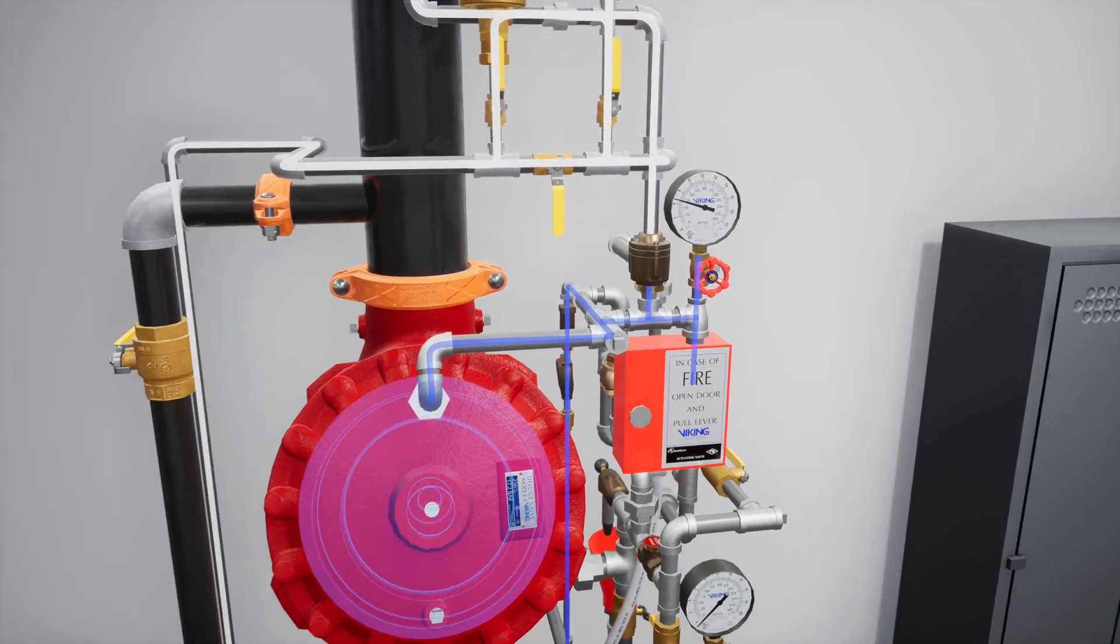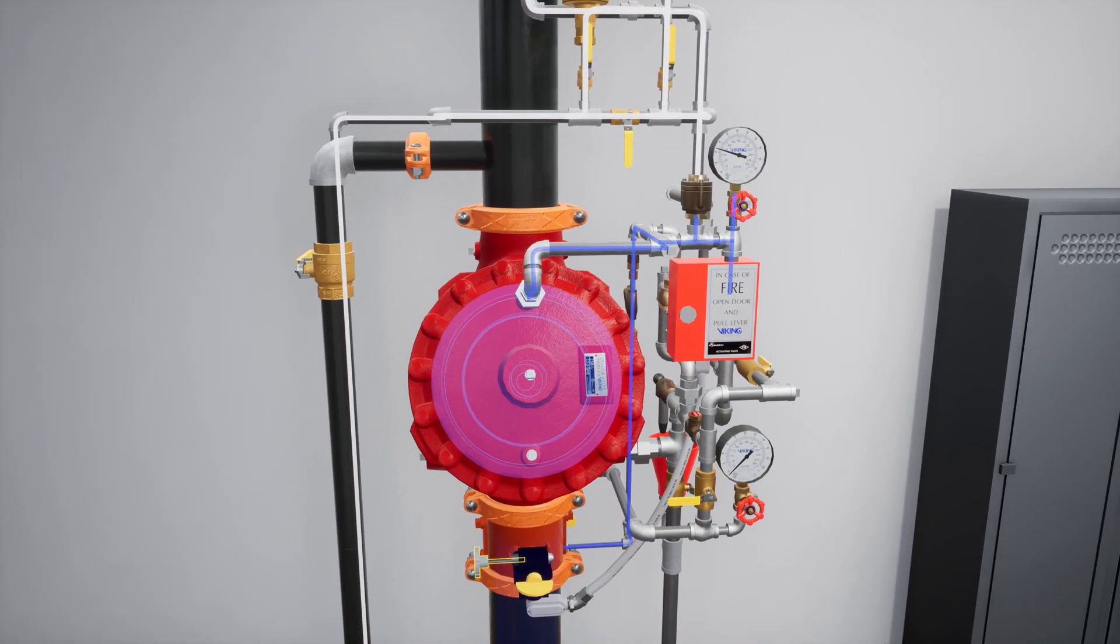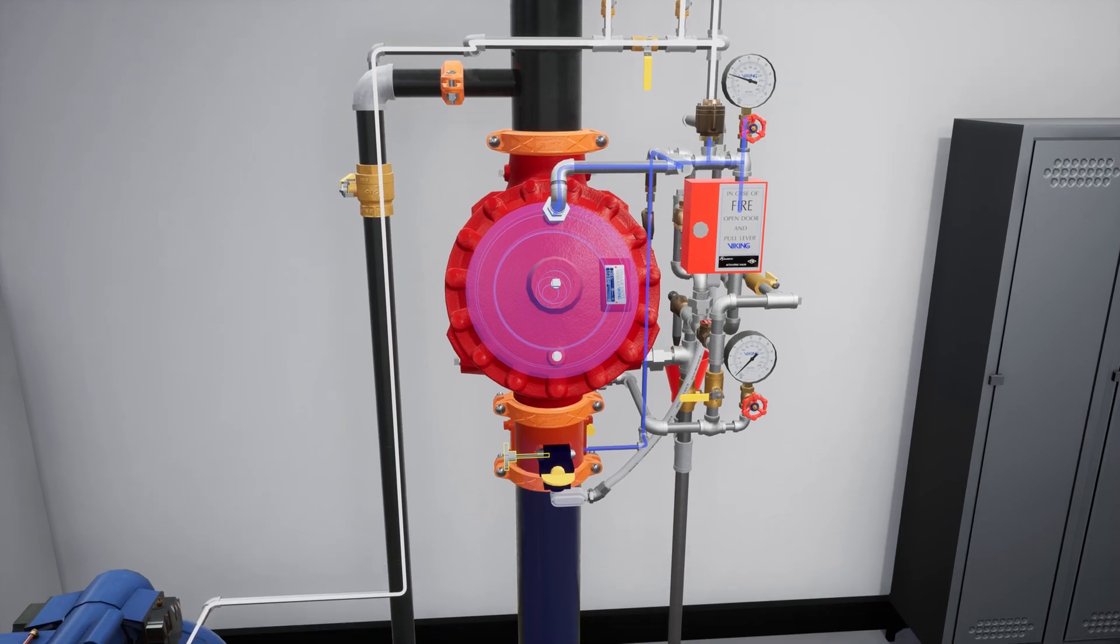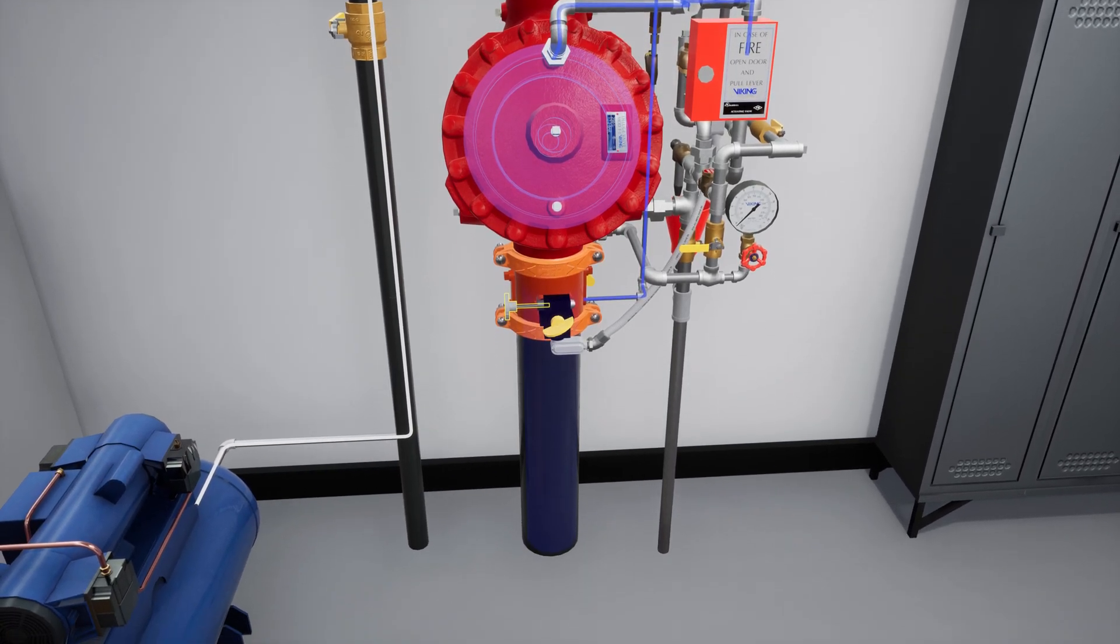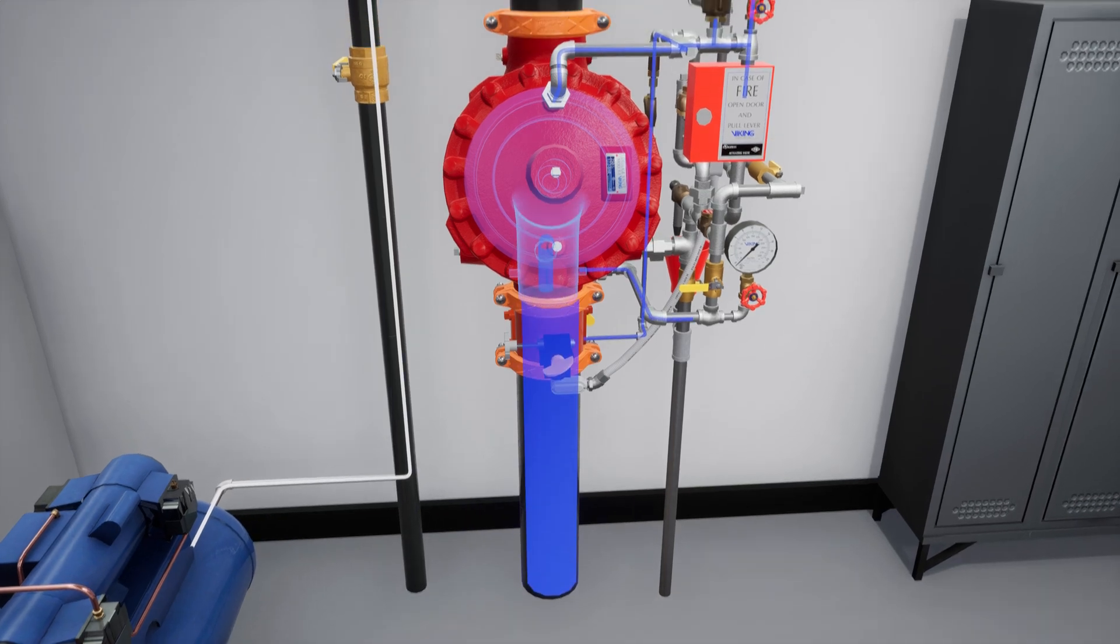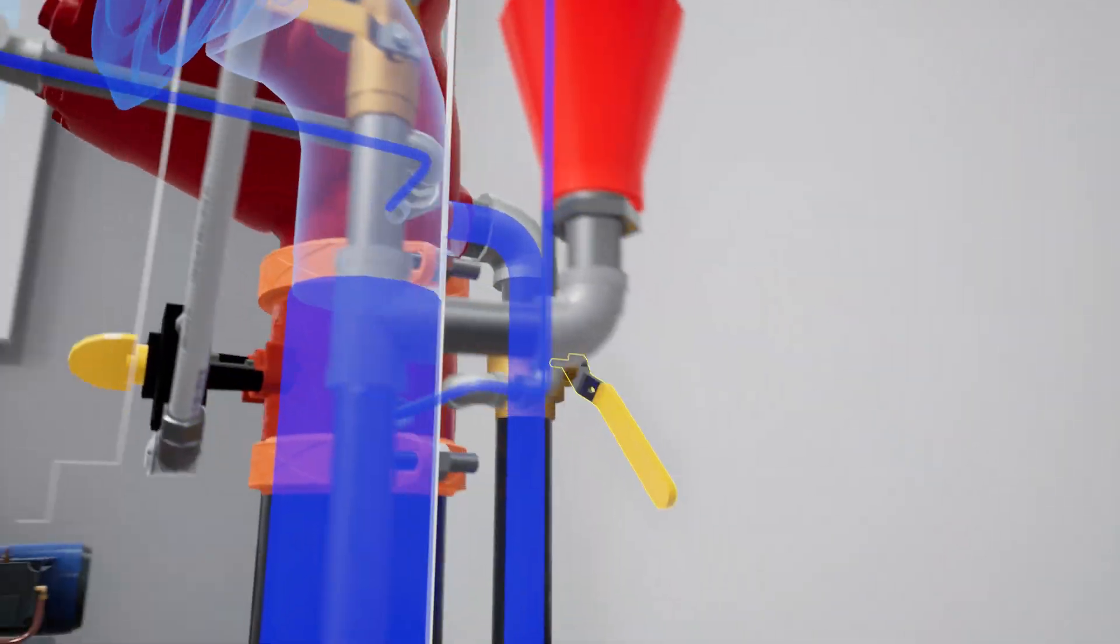Once water pressure has been reestablished in the prime chamber, slightly open the water supply control valve and begin reintroducing water into the system. Once flow has been established, close the flow test valve completely.